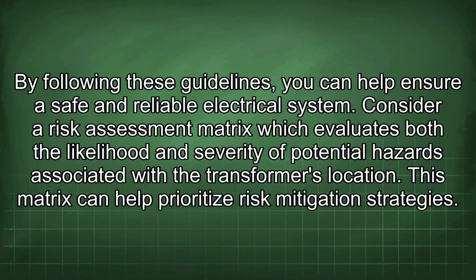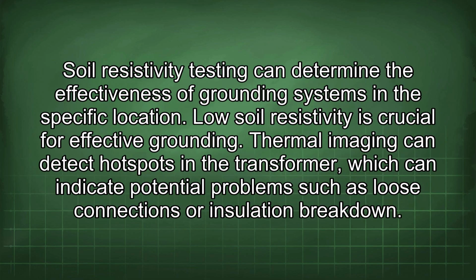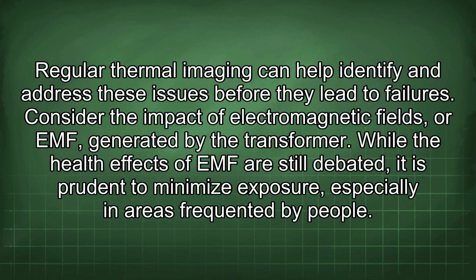Consider a risk assessment matrix which evaluates both the likelihood and severity of potential hazards associated with the transformer's location. This matrix can help prioritize risk mitigation strategies. Soil resistivity testing can determine the effectiveness of grounding systems in the specific location. Low soil resistivity is crucial for effective grounding. Thermal imaging can detect hotspots in the transformer, which can indicate potential problems such as loose connections or insulation breakdown. Regular thermal imaging can help identify and address these issues before they lead to failures.